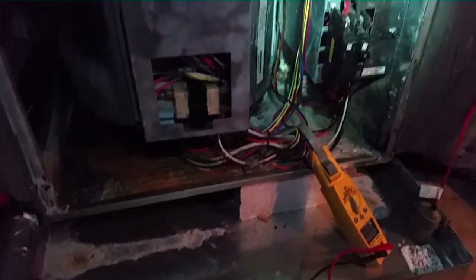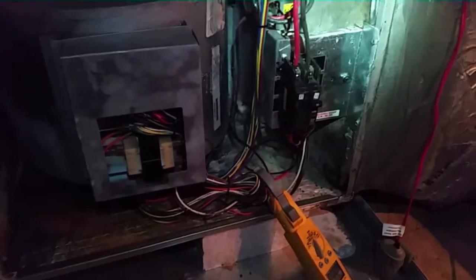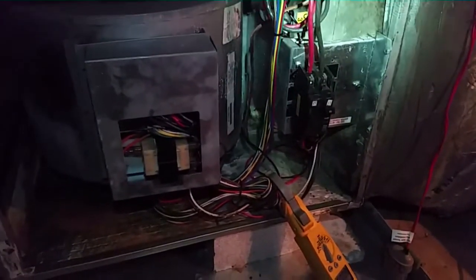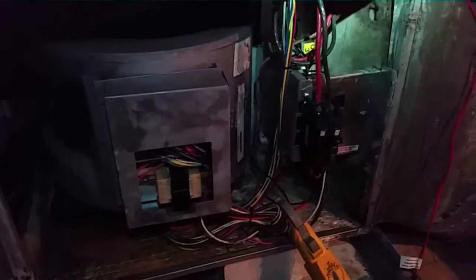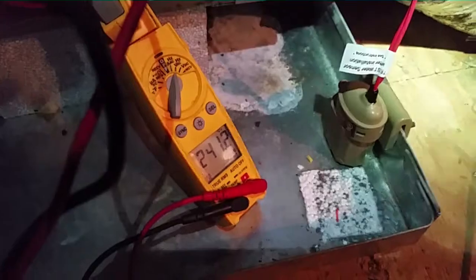And I actually slid the door into place except for a small section here where the meter was, kind of sandwiched it in place. So we're going to go with 1 amp. So we're running about 38 amps right now as far as heat strips. We'll take that and get our voltage, then we can multiply that out to get our watts. Our voltage is 241.7 here.